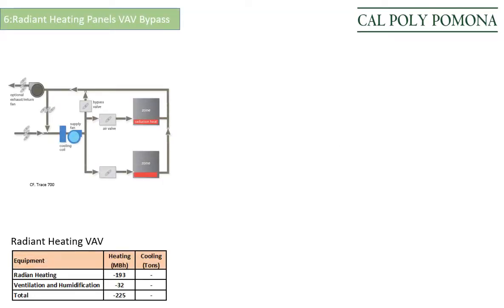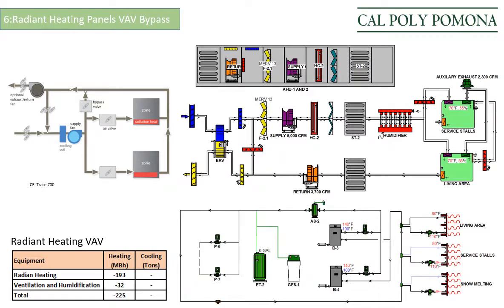During the peak hour, outdoor air temperature is 24 degrees Fahrenheit. If sensible and latent heating loads are dealt with separately, supply air can be reduced by 67% compared to the ASHRAE 90.1 baseline by minimizing the outside air damper to 20%.